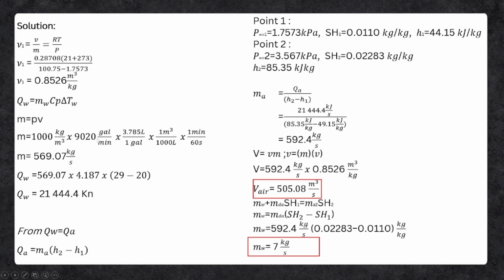Ang given natin dito is yung volume flow rate, which is 9,020 gallon per minute. Iconvert lang natin siya para maging kilogram per second. Multiply mo yung gallon, convert natin into liter. For every 1 gallon, there is 3.785 liters. And for every 1,000 liters, meron 1 cubic meter. And for every 1 cubic meter, meron namang 1,000 kilogram. Convert lang natin ang minute into seconds. Ang makukuha nating sagot is 569.07 kg per second.